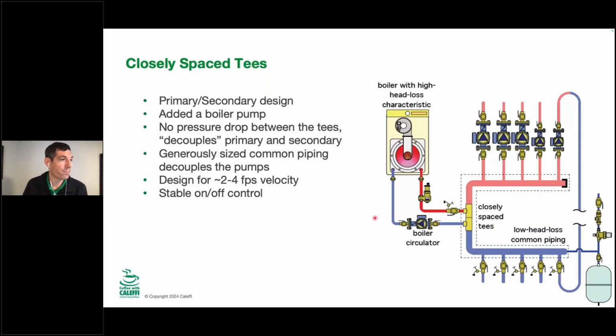So when I talk to people, especially people on the phone, and they're describing the problem they're having with a primary, secondary piping system where no temperature, no flow, no heat, whatever it might be, in this drawing right here, which side of that is the primary and which side is the secondary circuit? Because if you're not on the same page when you're trying to explain this to somebody, I could be talking about the boiler side doesn't have any flow, and I would say, well, look at that pump. And he's thinking, well, I'm talking about the distribution piping. So here's the right way to know that and to explain it. Whichever side has the expansion tank connected into it is the primary loop.